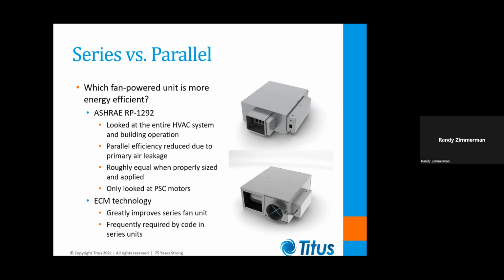And of course now energy codes are stating that you have to have a minimum fan efficiency of at least 70% in any product where the fan runs during the cooling mode. And although they can't require you to use ECM, that's the only technology that will give you that kind of efficiency. So in many places, you must provide series fan units with the ECM. But in those same markets, you can still use the parallel unit with the PSC motor because the motor only runs during the heating mode.